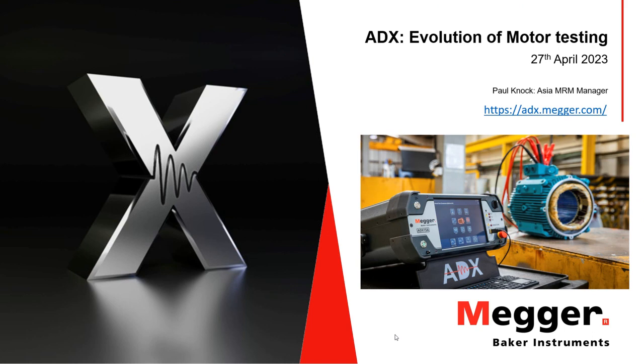And also with the latest interest from predictive maintenance and data being all important, we now have the ability to store information and trend it over a period of time, looking for opportunities where we can spot issues before they occur and we can plan maintenance around them. This would give us the opportunity not to waste money on maintenance activity that's not warranted, or even potentially be able to pick the right time when the unit does need attention prior to a failure, rather than run to fail, for example. So different maintenance strategies can lend different kinds of, should we say, cost savings to using the equipment.